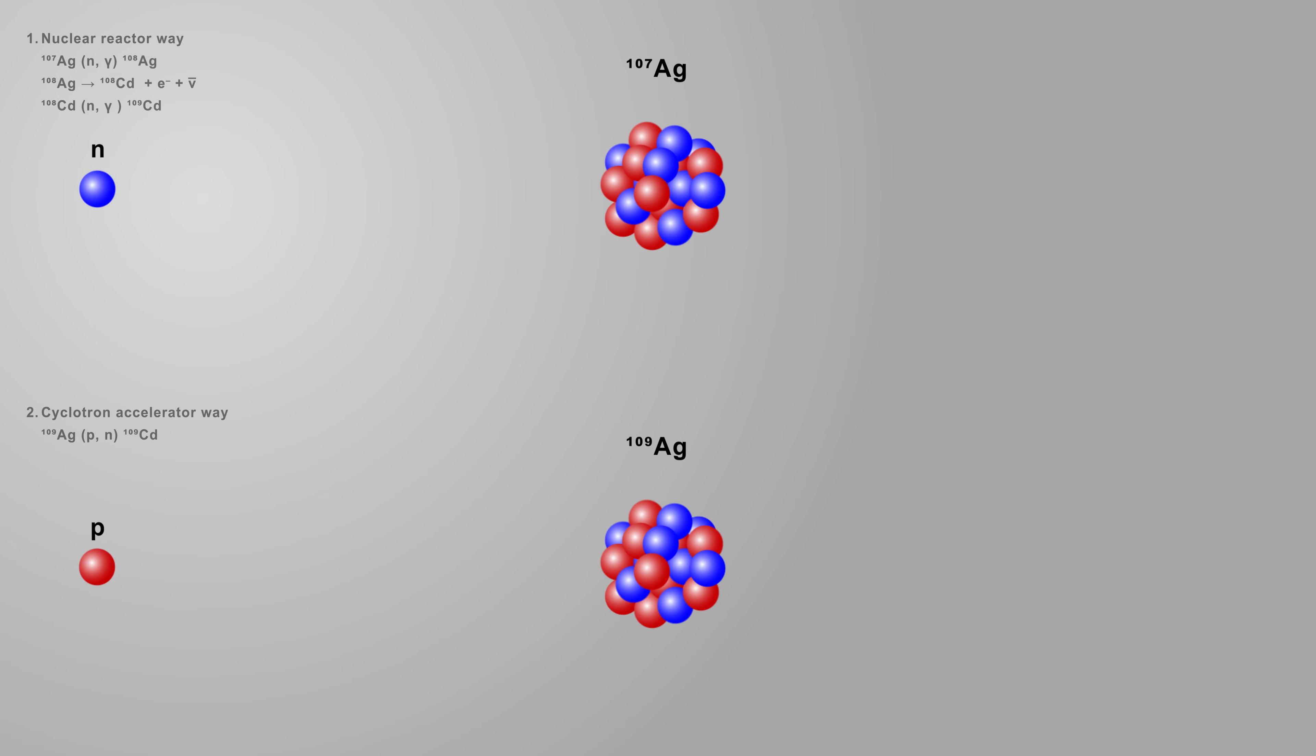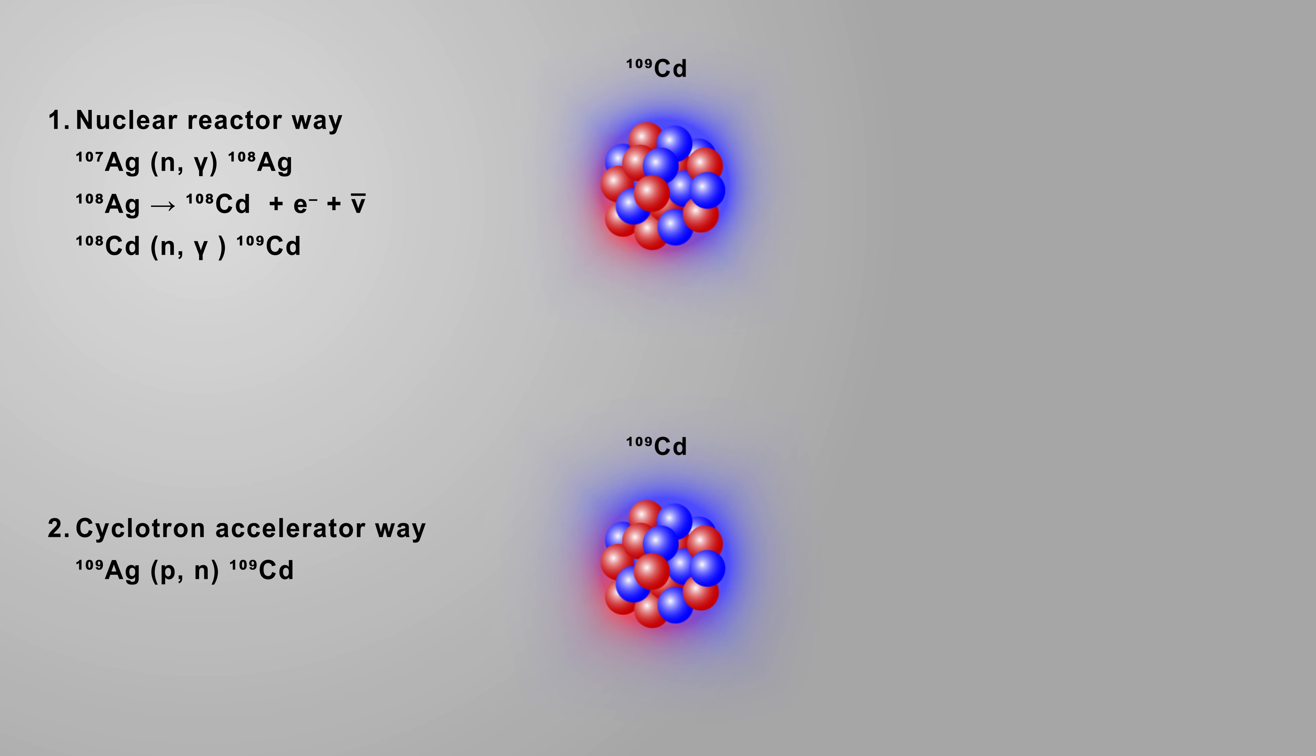Cyclotron-produced cadmium-109 is roughly five times more expensive than its reactor-borne version, but it yields ultra-pure, carrier-free, very high-specific activity radioisotope. This matters a lot when manufacturing a radiation source, allowing for much smaller and much higher output sources.